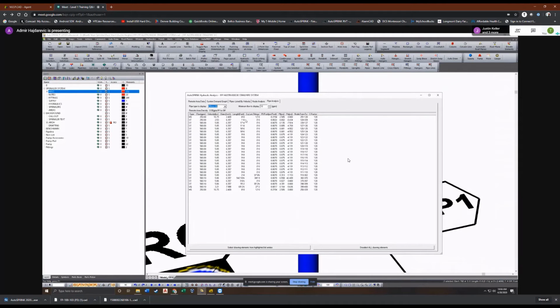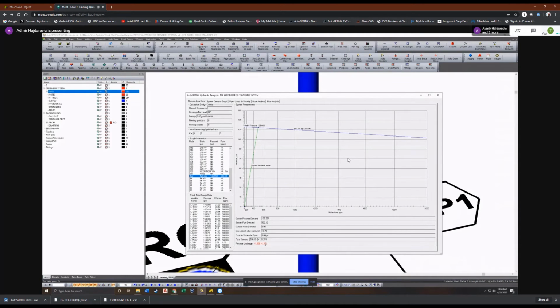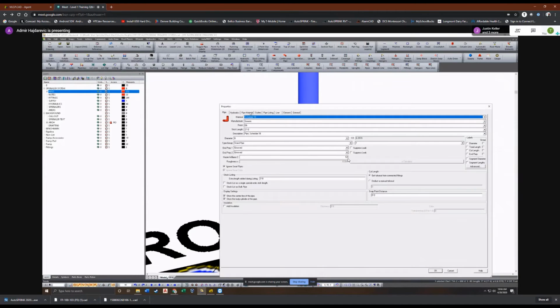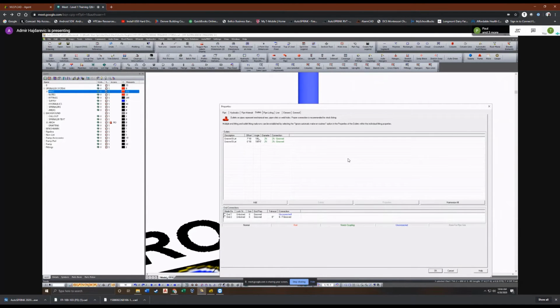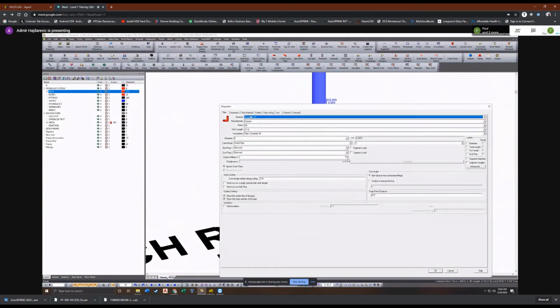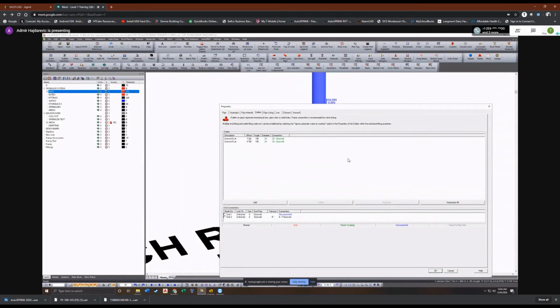Now the equivalent length. Let's take a look at that. So you can see it's not calculating any length there, but it is still including the 12 feet T loss. That's what's killing us, giving us that 1 pound, 2 pound loss. Right. So let's close out of this and then open the properties of the standpipe. This is going to be really tricky because we have a ton of outlets on this. Oh no, we just have the two segments. Beautiful, perfect. I got nervous, there's going to be like 30 or 40 of these things.